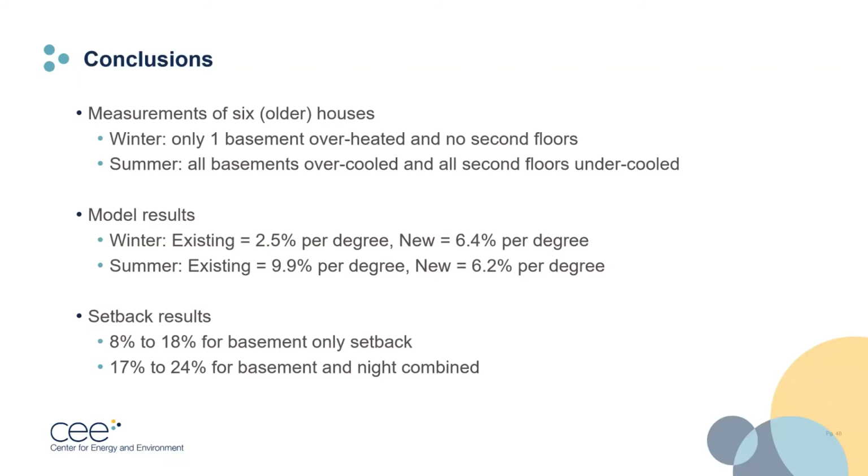The heating savings was about 6.4% per degree of average temperatures for the basement and the second floors, and it was about 6.2% per degree for the cooling savings.